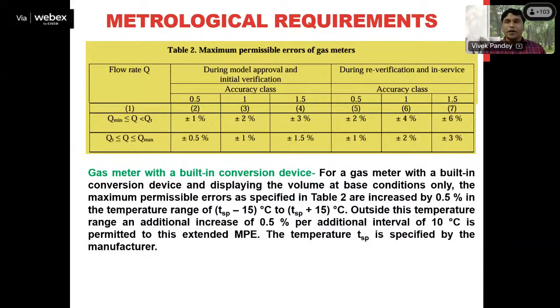You can see in this table that it specifies the maximum permissible error for gas meters. This maximum permissible error table is divided in two segments. One is for model approval and initial verification, and another one is for re-verification and in-service inspection. When we talk about model approval, it is done by the regional reference standard laboratories in our country. They give the model approvals for different weighing and measuring instruments, or you can say weights and measures. And based upon the accuracy classes of the gas meters, whenever a gas meter is checked during model approval and initial verification, initial meaning first verification, fine.